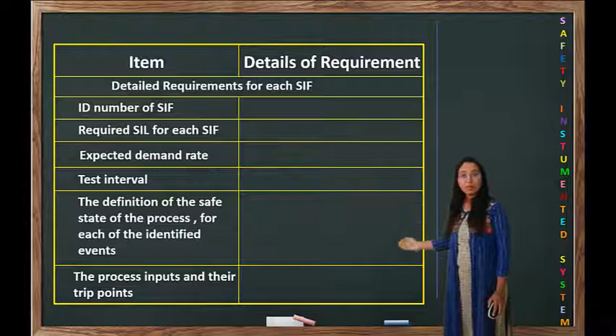So in SIF, ID number of SIF, required SIL for each SIF, expected demand rate, test interval, the definition of the safe state of process for each of the identified events, the process inputs and their trip points. Next, the normal operating range of process variables and their operating limits, the process outputs and their actions, the functional relationship between process inputs and outputs, including logic, math functions, and other required permissives. Selection of de-energized to trip and energized to trip.